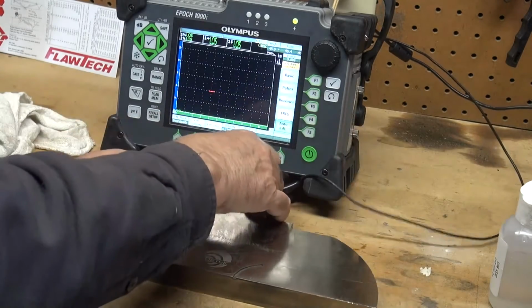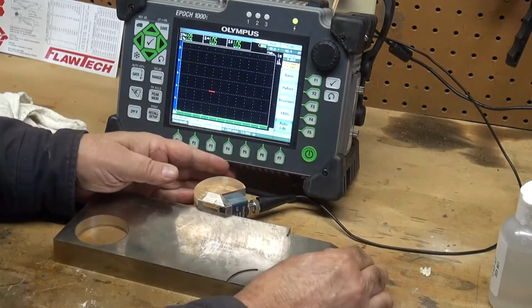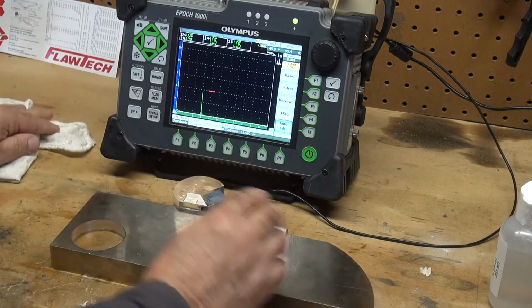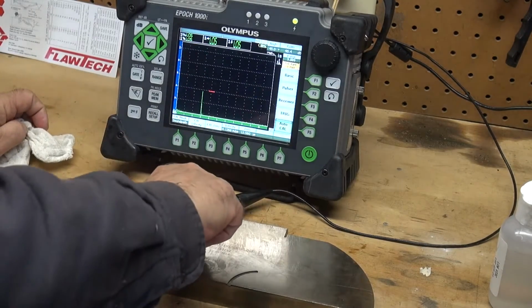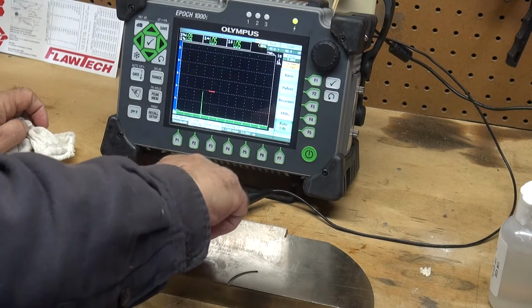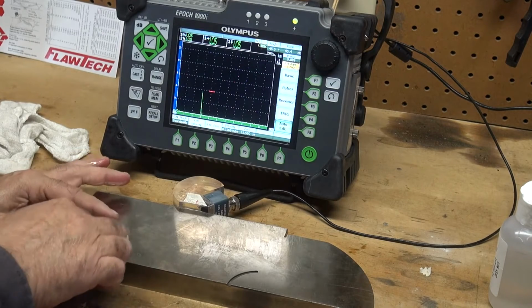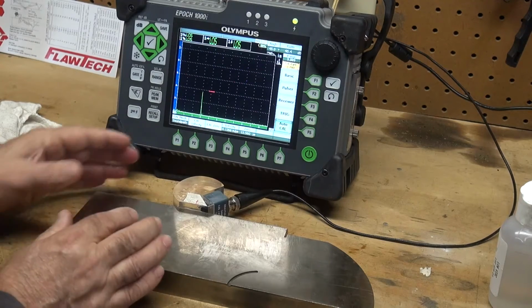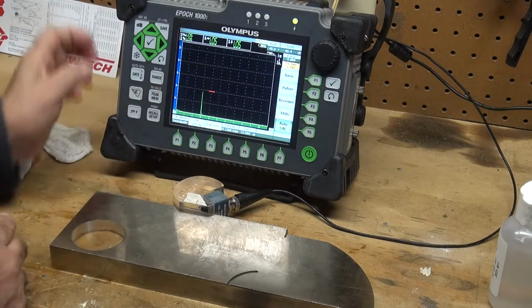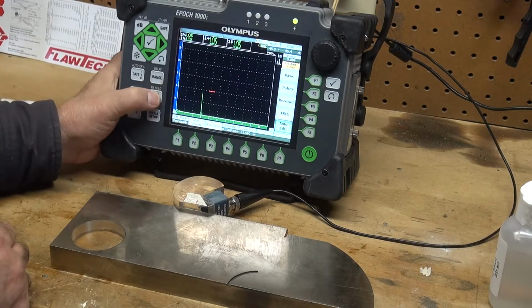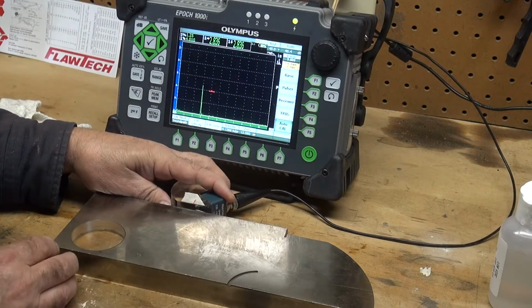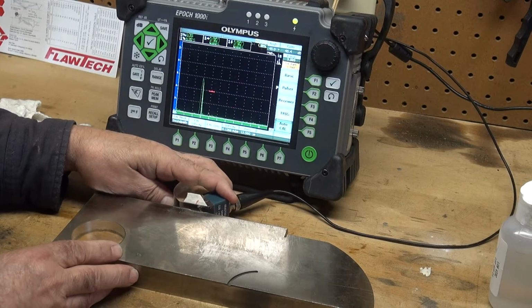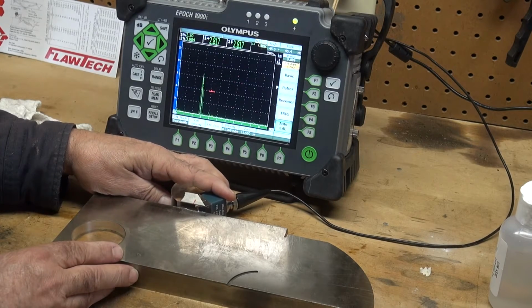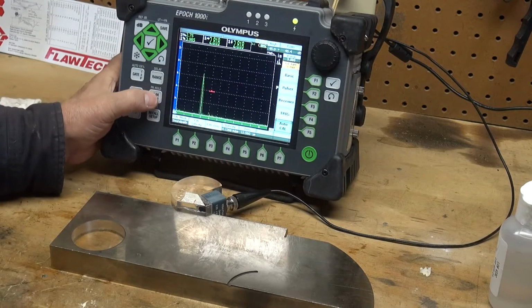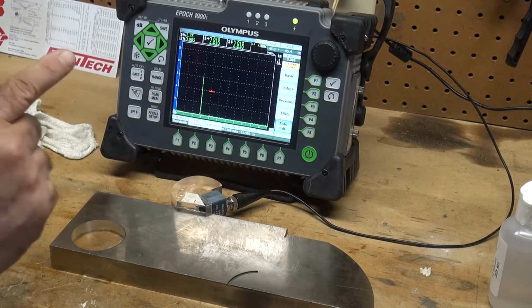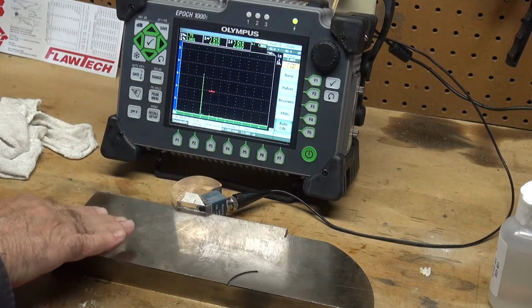I'm going to put my transducer basically in the 45 degree area, and it is shooting that sound at 45 degrees down to the radius here in this large hole. You can see a reflector. I want to hit my peak memory, and move back and forth and find where my maximum energy is. Right here. I'm in the middle of my curve right there. I turn off the peak memory.